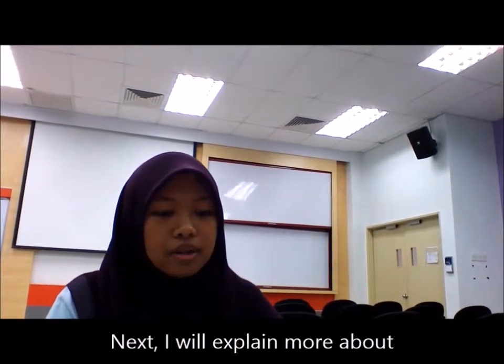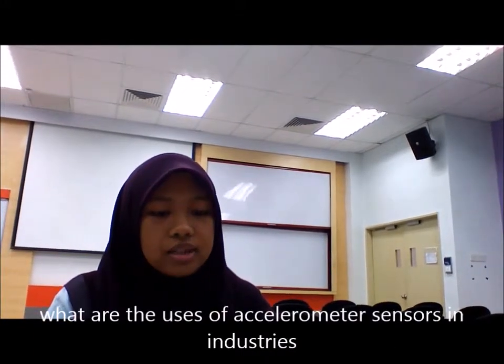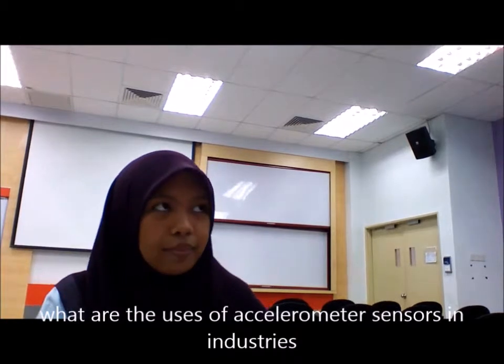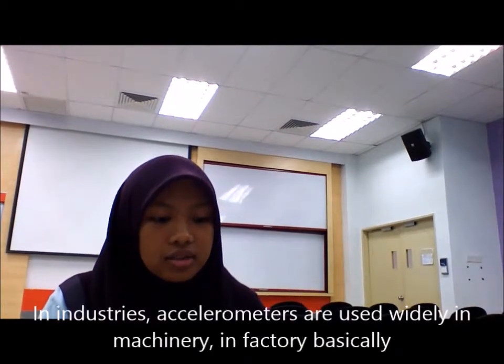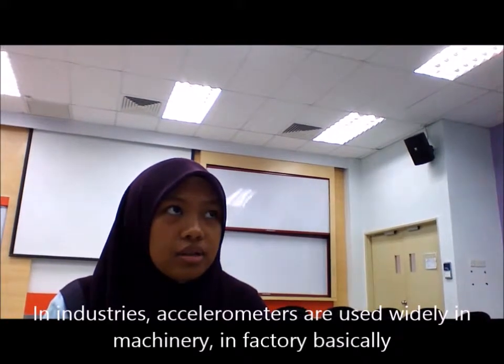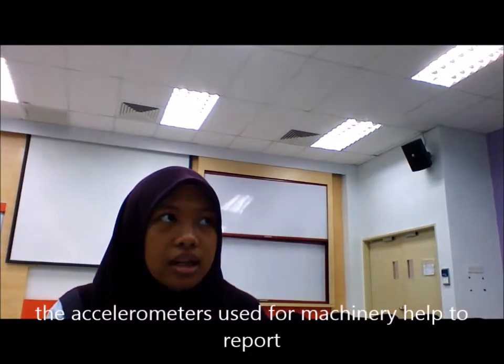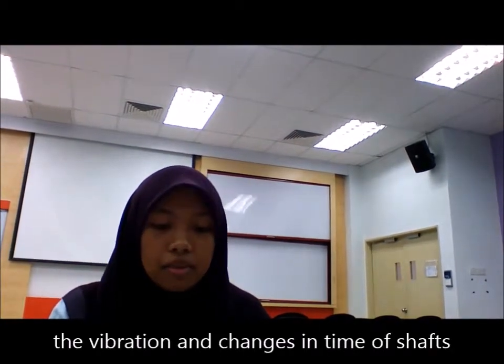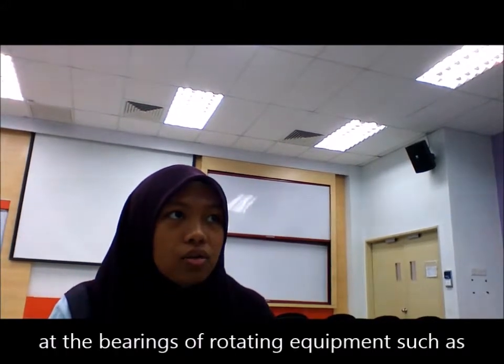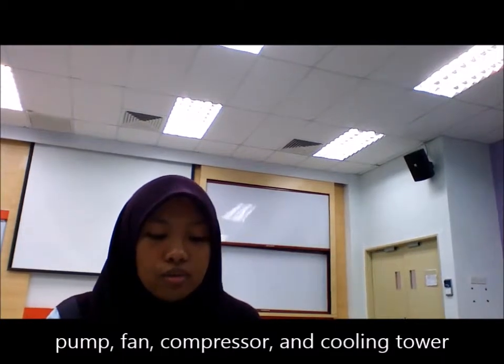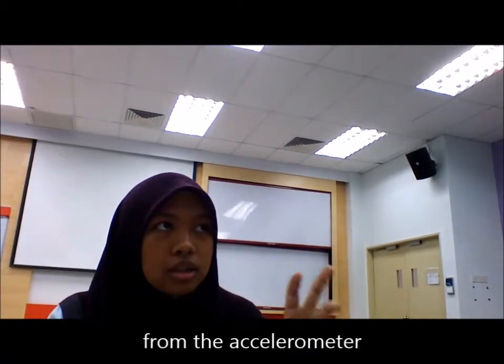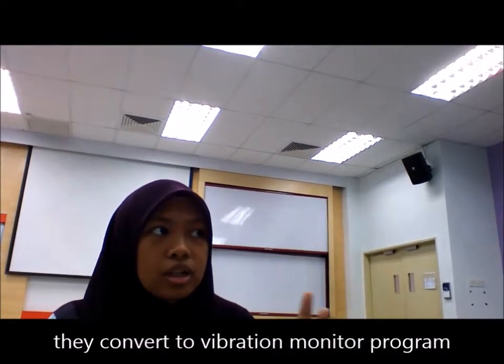Next I will explain more about the use of accelerometer sensors in industry. In industry, accelerometers are used widely in machinery, in factories basically. The accelerometer used for machinery helps to report the vibration and changes in time of the shaft at the bearing of rotating equipment such as turbines, pumps, fans, compressors and cooling towers. From the accelerometer, the data is sent to a vibration monitoring program.